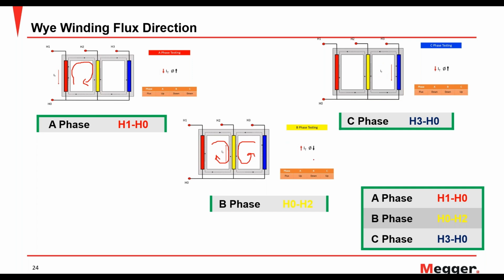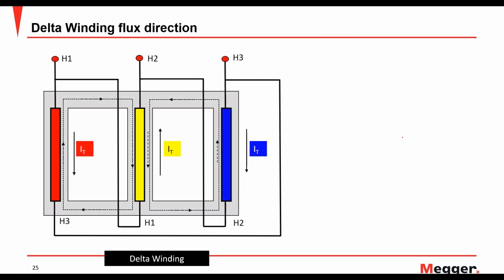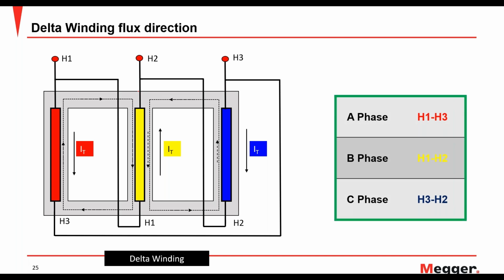So it's aligning with all the three. If you notice, it's aligning with all the three different phases. And that's how you are making sure that you are moving in the direction of the flux and not working opposite to it. That'll help you achieve the winding resistance measurement much faster than anything else. And that was for Y winding.